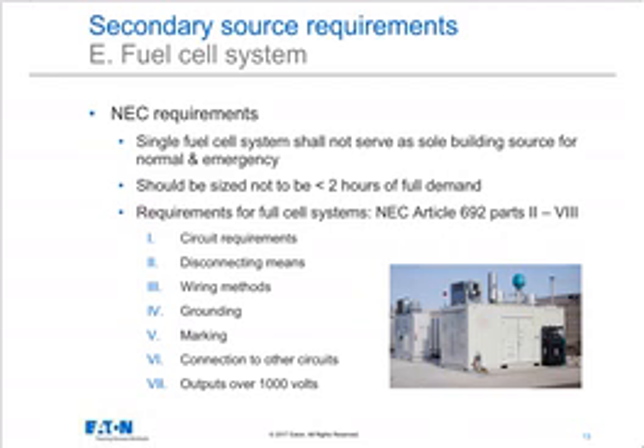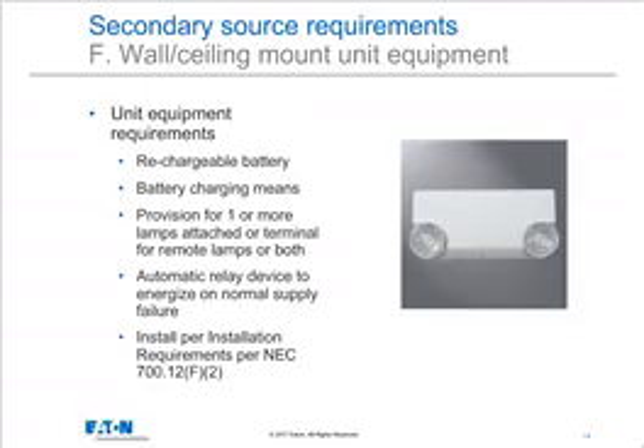Now the last one is the wall and ceiling mount equipment that we talked about before, and the requirement for those is that the battery needs to be rechargeable. Traditionally, these were relatively large and heavy batteries that dictated the entire size of this wall-mounted box. But if you pull a new one off the wall today, you will open it up and see that it has a relatively small nickel metal hydride or even a lithium battery that often runs as much as 2.5, 3 hours instead of the 90-minute minimum, and is relatively small, lightweight, and easy to replace. So that's the good news.